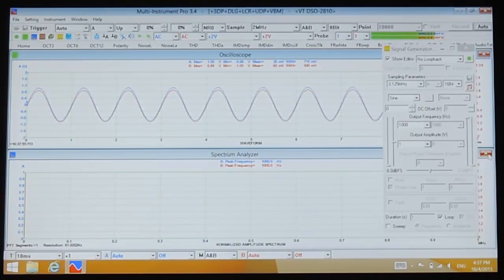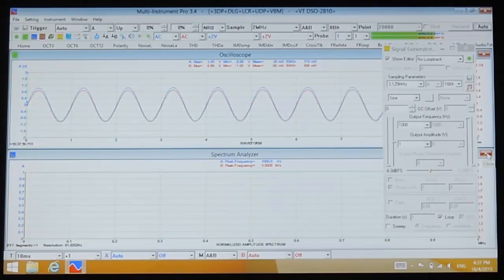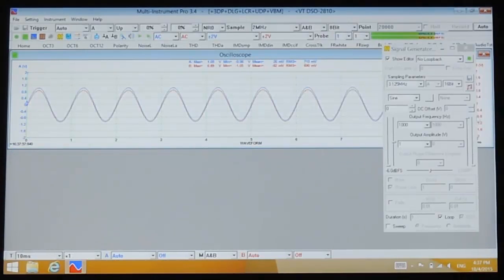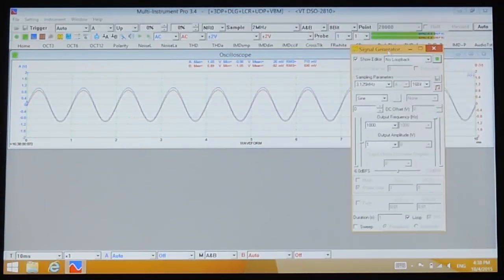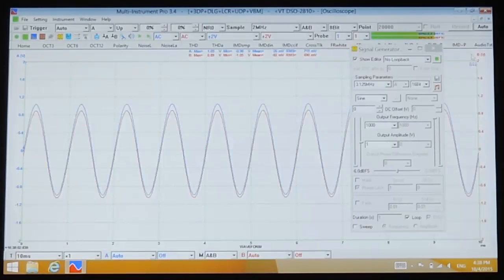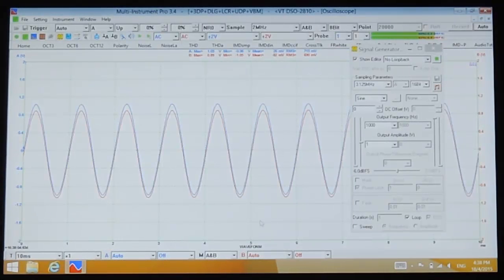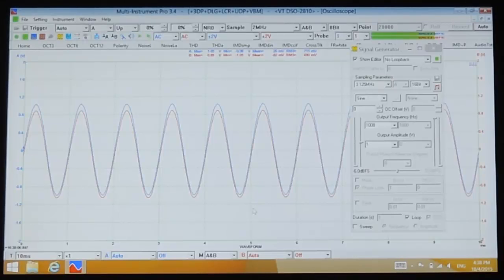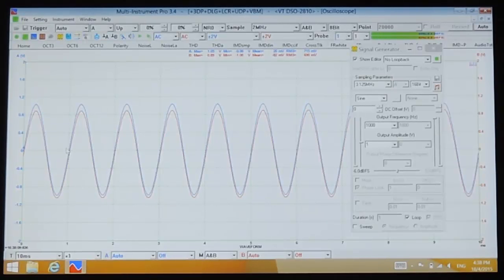Now the oscilloscope switches to the measuring range of plus minus 2 volts. As you can see from the screen, the two waveforms measured by the two channels do not match very well. Now we follow the recalibration procedure described in the hardware manual to recalibrate this particular voltage measuring range.